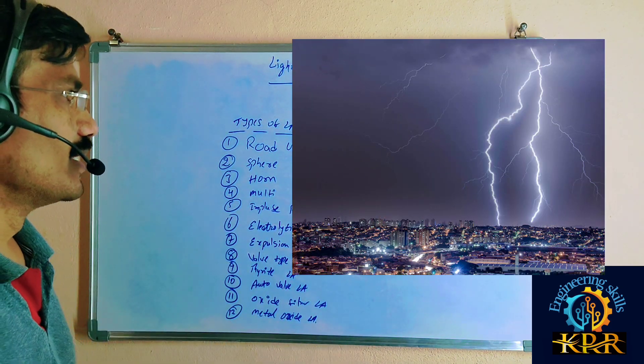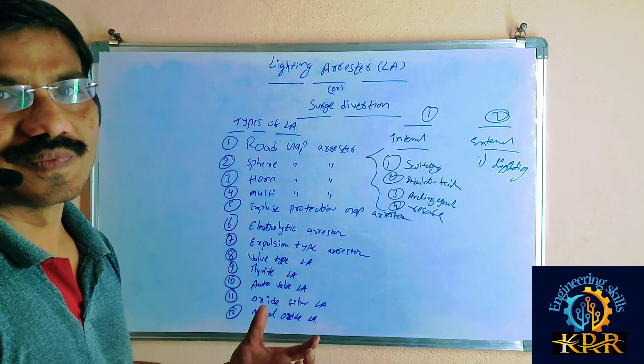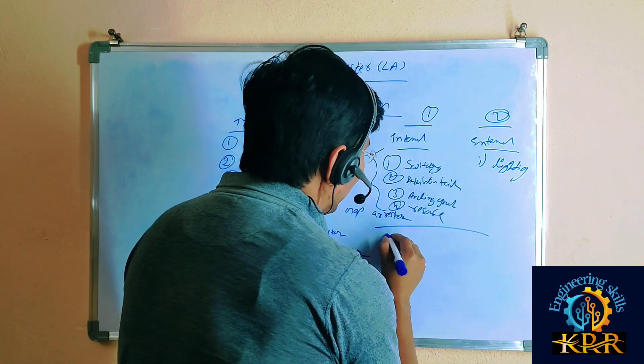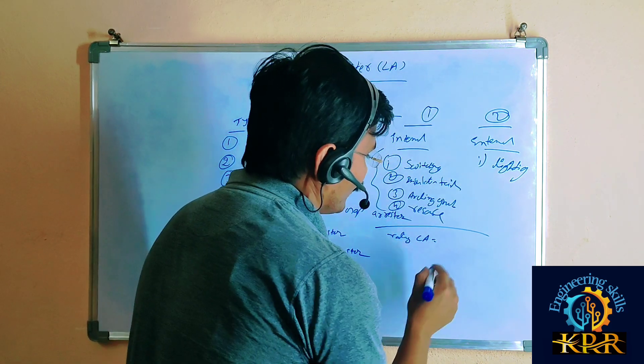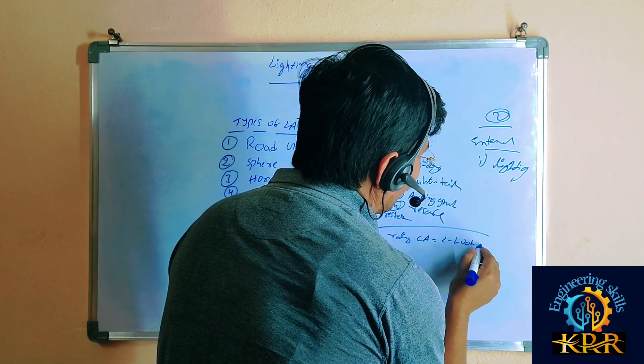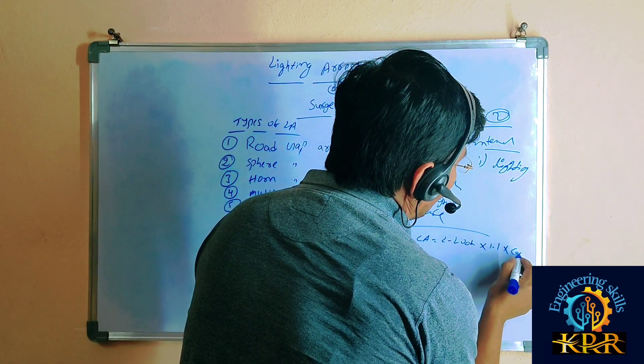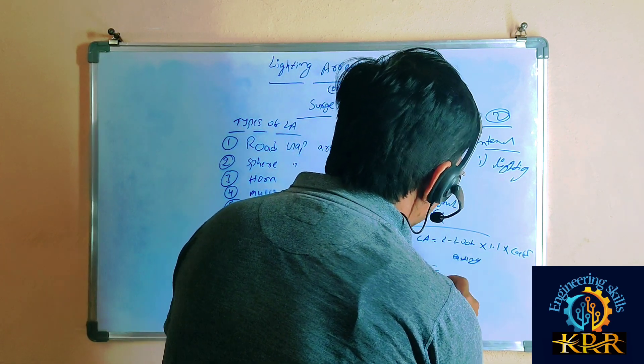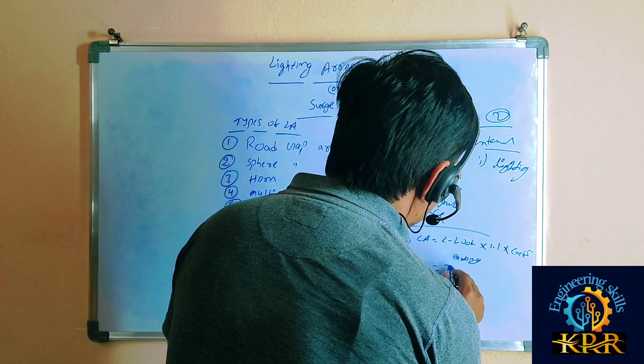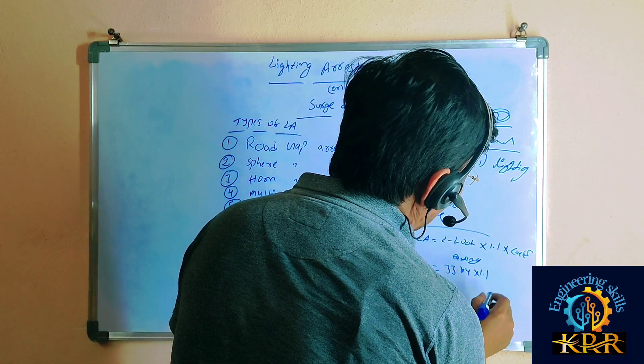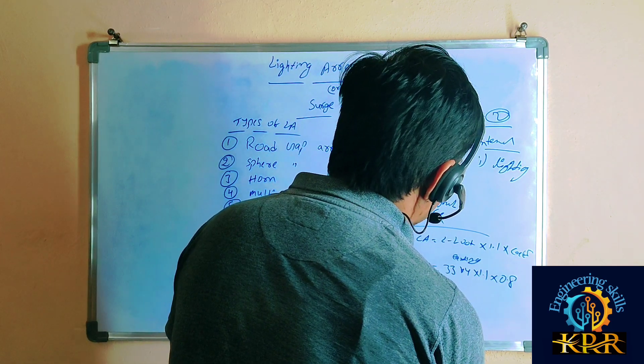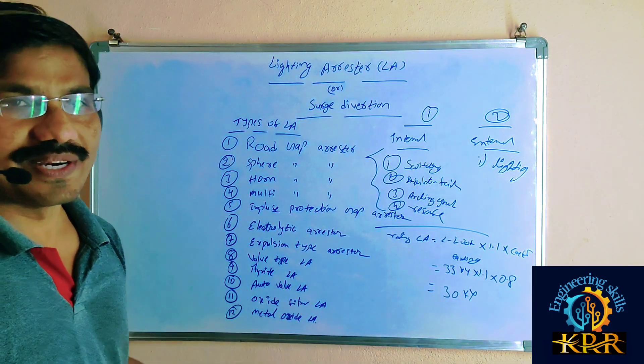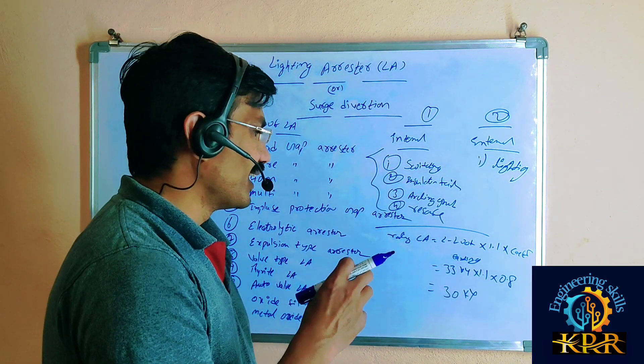Basically, how to calculate the rating of lightning arrestors: the rating of a lightning arrestor is equal to the line-to-line voltage multiplied by 1.1, multiplied by the coefficient of grounding, which is 0.8. For example, if the operating voltage is 33 kV, the lightning arrestor rating required will be 30 kV.